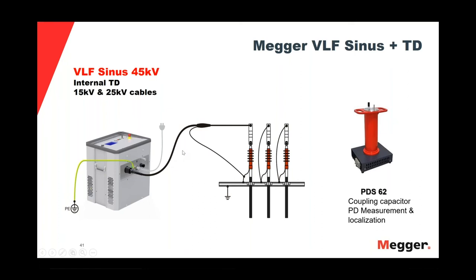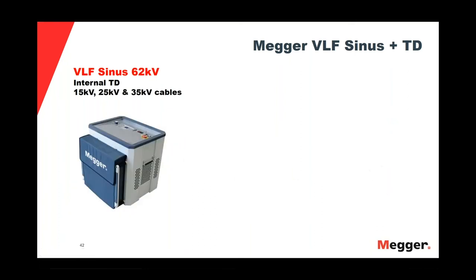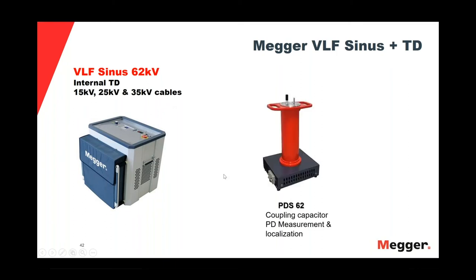The last unit we have is the VLF Sinus 62. This also has an internal tan delta test. We use the unit to do a VLF test in 15, 25, and 35 kV cables. And of course, also we have the PDS-62 coupling capacitor to measure partial discharge and do the localization of the partial discharge. Okay.